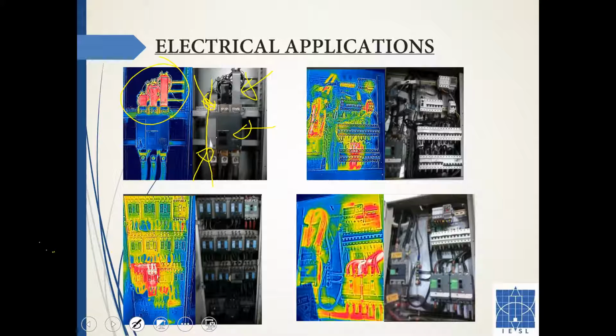In this second picture we have a typical overload situation. It could be a loose connection here, or a throughout overload situation, but from the looks of it, it's a connection problem. Here we can see another overload problem - in this MCB we can see hot contacts inside, as shown in this image and the lower one here.